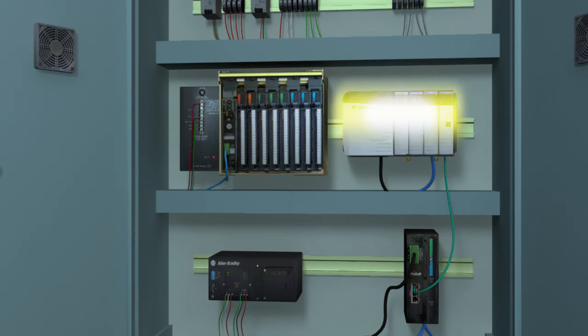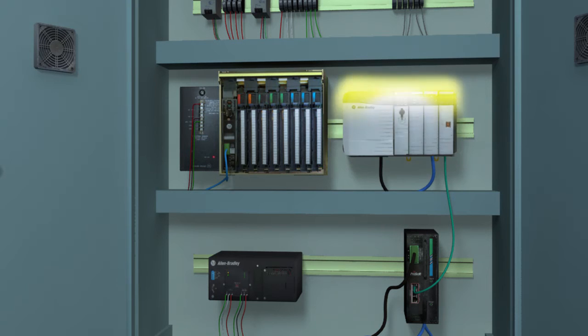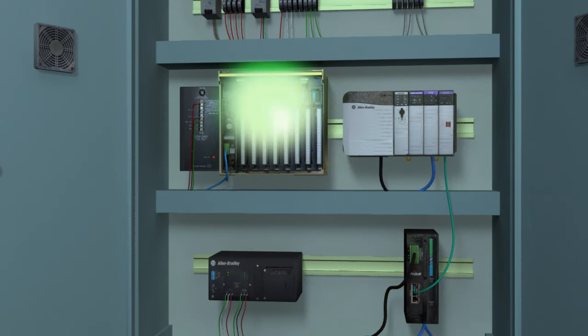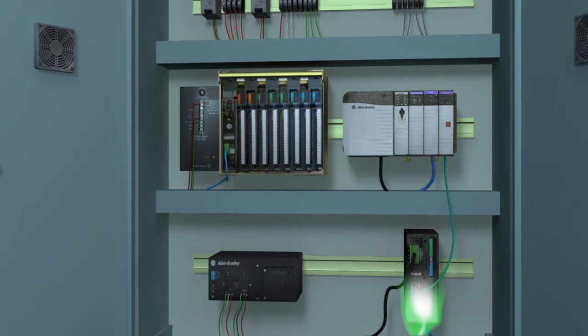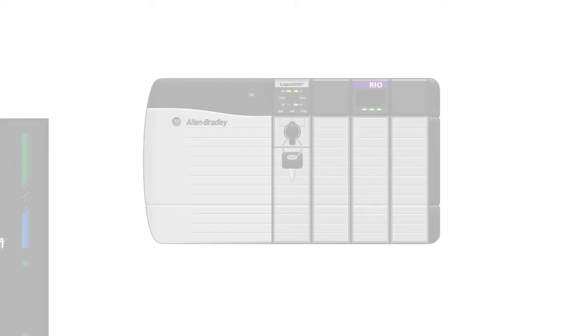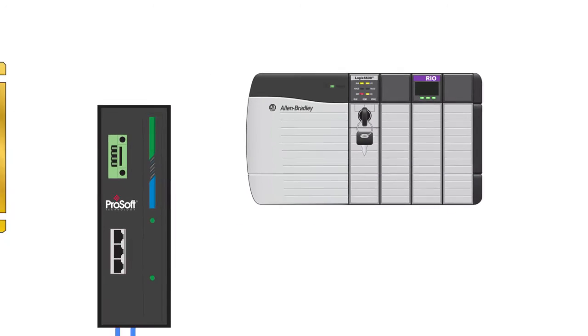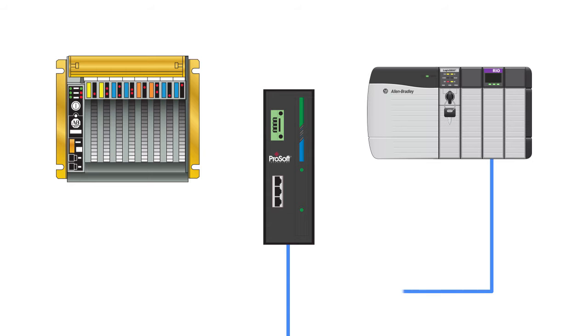A ControlLogix system can be configured and the PLC5 program converted, while your remote I/O system continues to run as normal. When you have your program converted, a 1756 RIO module can be used in the ControlLogix system to take control of the remote I/O devices during regularly scheduled downtime.